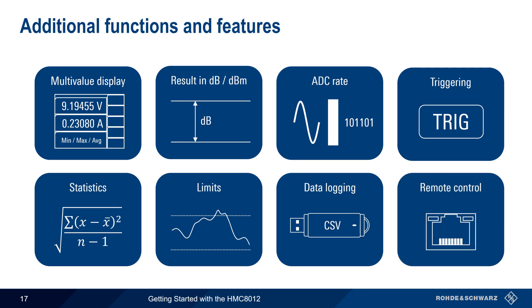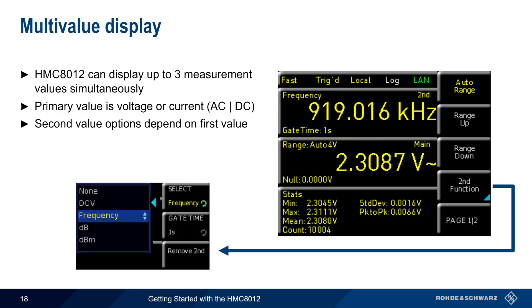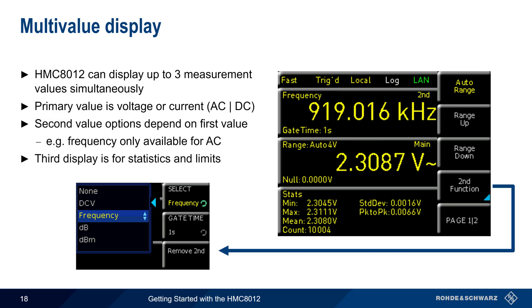Let's start by looking at the HMC's multi-value display. For some measurements, the HMC 8012 can display up to three measurement values simultaneously. The primary value in the middle of the display is voltage or current, either AC or DC. Pressing the soft key second function enables display of a second value – for example, frequency is only an option when measuring AC signals. The third display at the bottom of the screen is for statistics and limits.